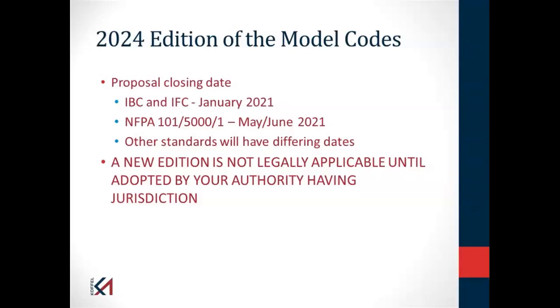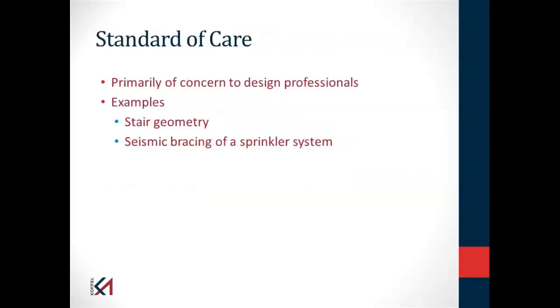But as a facility person, clearly one important thing to recognize is that, despite what NFPA or the ICC does, none of these new editions have any legal applicability to your facility unless they're adopted by a fire marshal, a building department, or state legislature, however that's done in your area. Somebody has to say, effective some date, we need to comply with the new edition, or some edition, of the I-codes or NFPA.